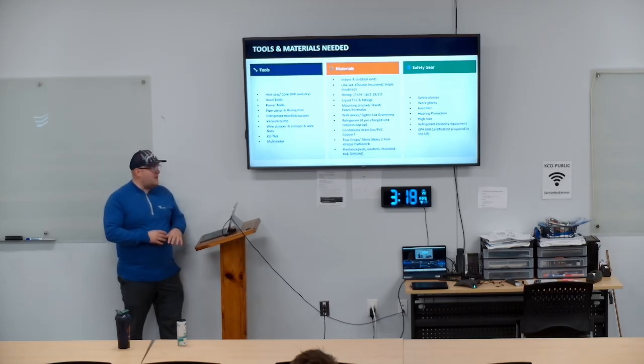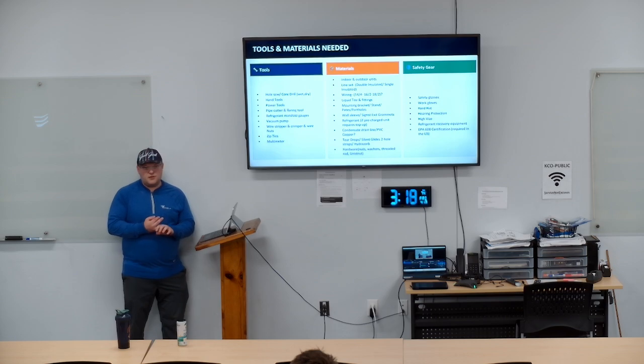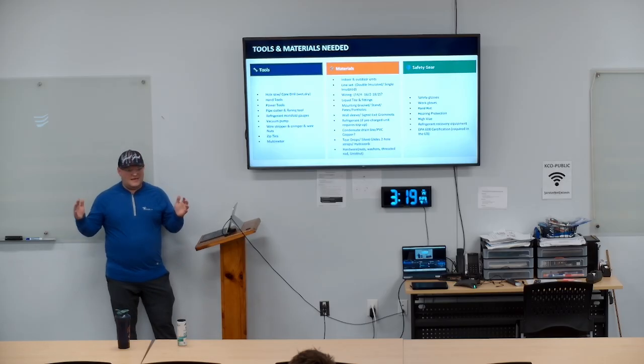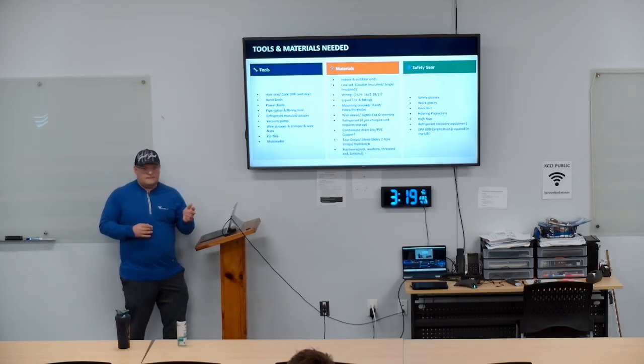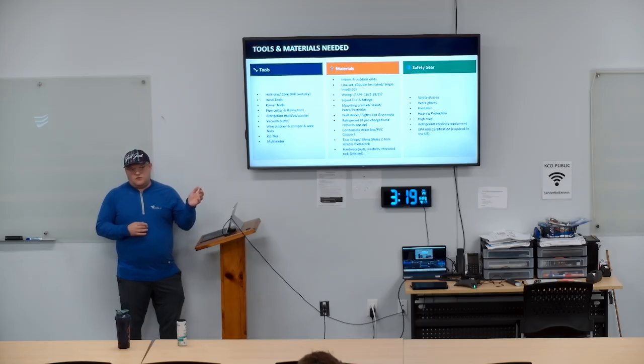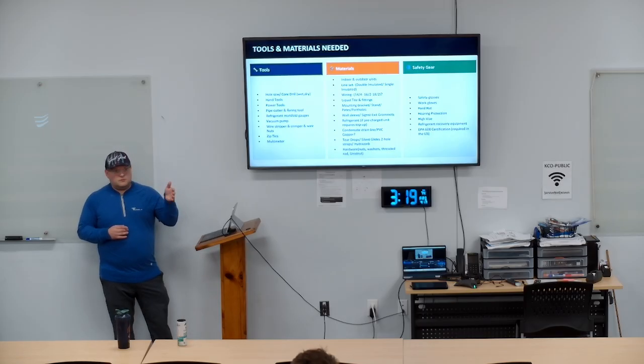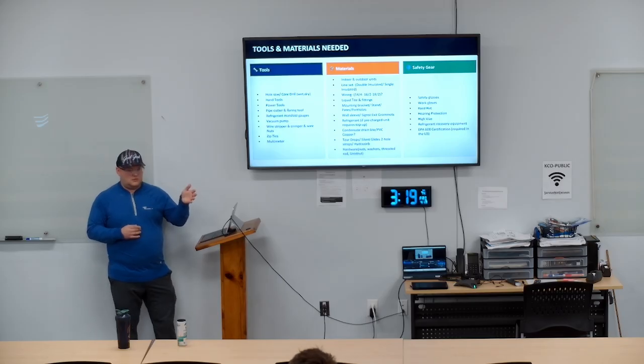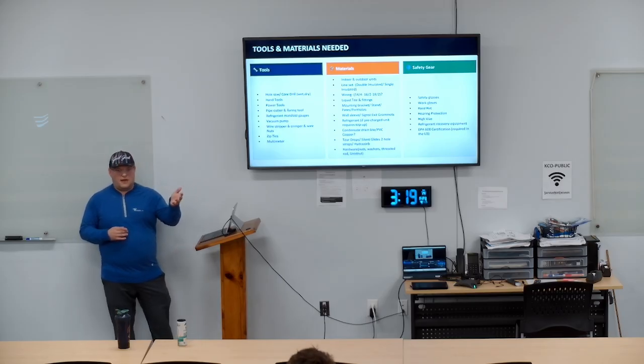Refrigerant: most splits come pre-charged, but again, the installation manuals will tell you if you need additional, and it's based off of line length. So if I've got a 100-foot liquid line, it'll say, okay, it's charged for 25 feet. Then it may say, for every foot additional over 25, you need to add 0.21 ounces. Well, then you would multiply that by whatever your additional footage is, and that's how many ounces you need to add to the system to run.